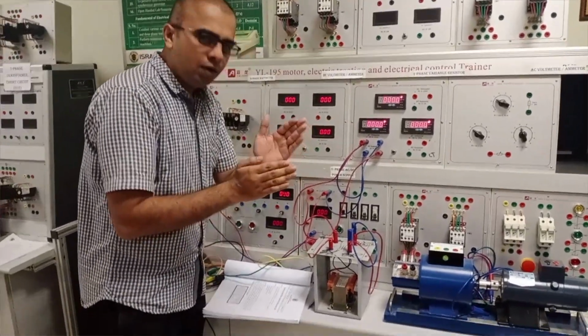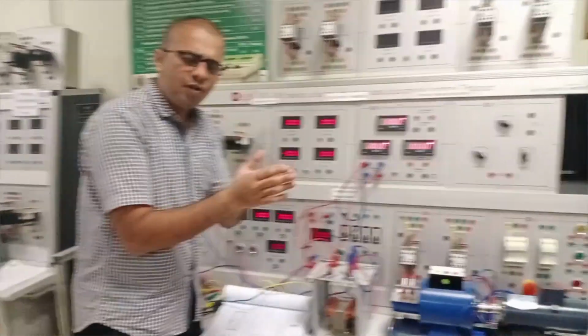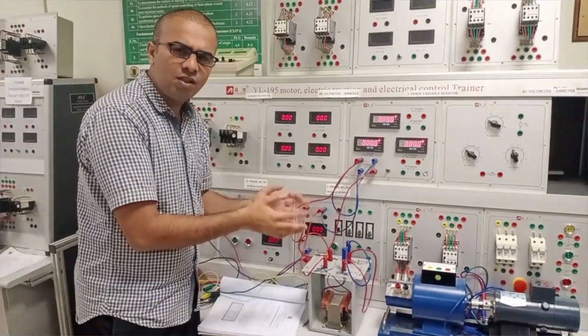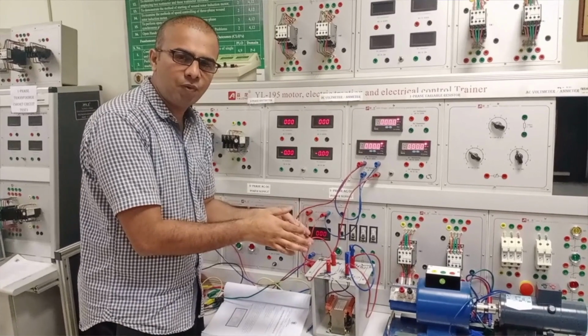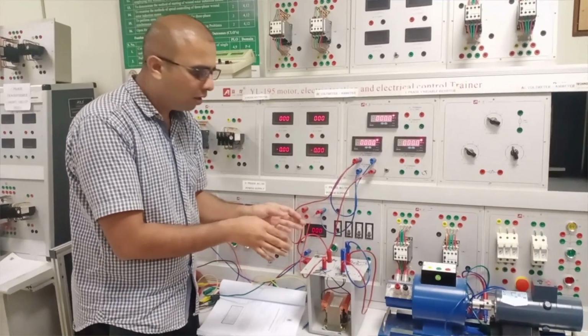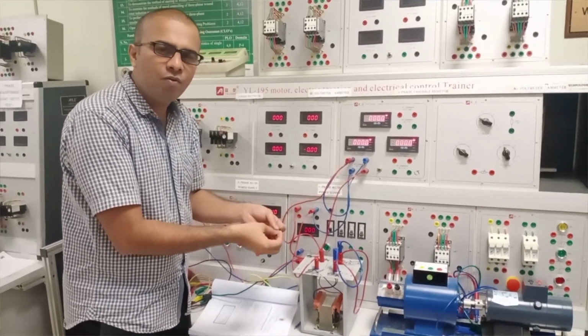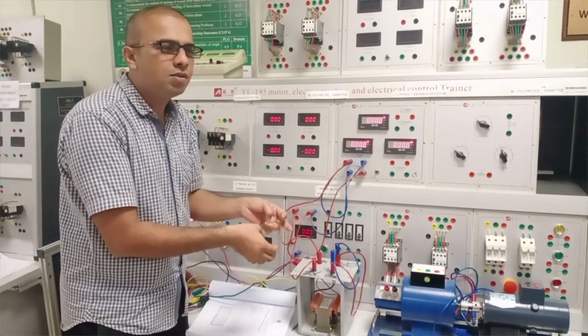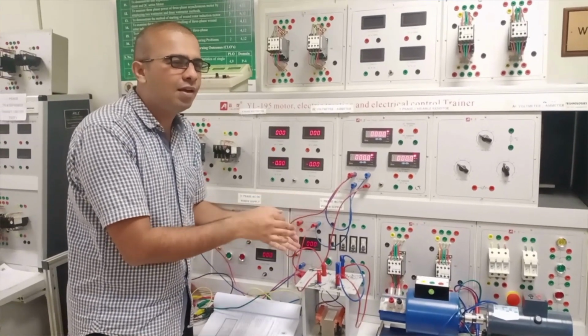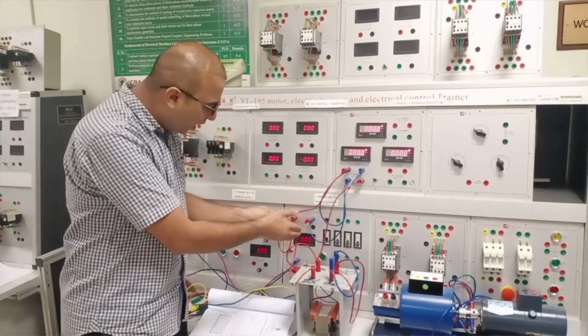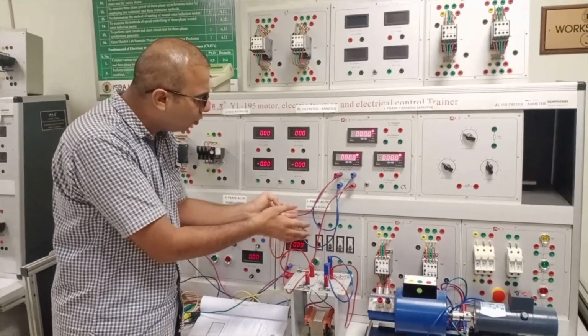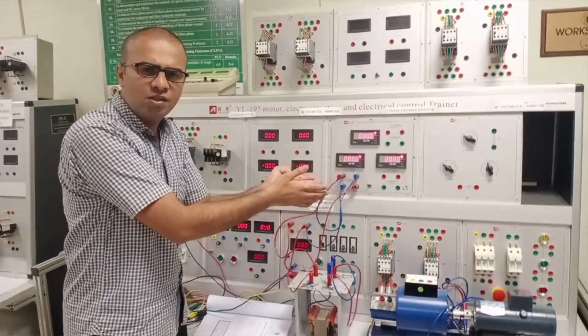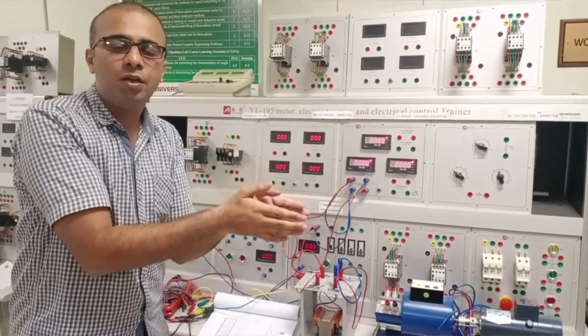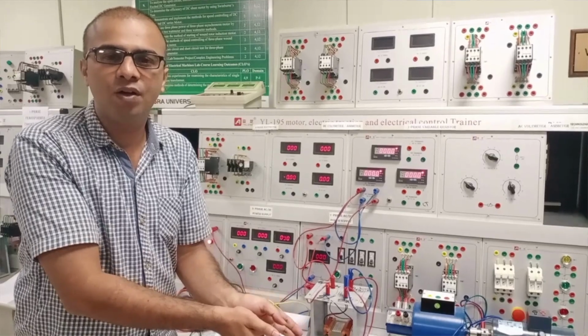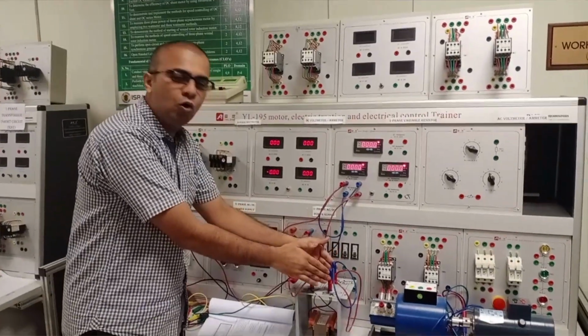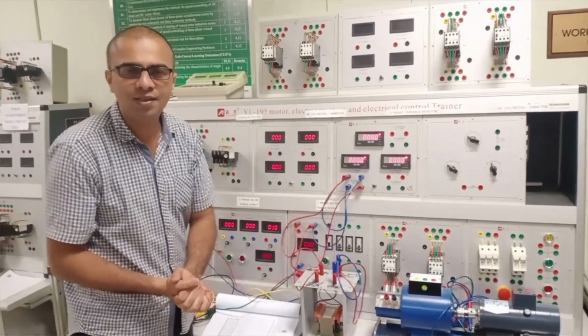Now 5 to 10% of the rated voltage, where 127 volt is the maximum voltage to be given to this transformer on the primary side. If we give a nominal 100 volts to this transformer, then 5 to 10% will be like 5 to 10 volts. Up to that 5 to 10 volts or 12 volts, the full load current starts flowing from the windings of the transformer. That full load current will be called the copper losses in the transformer, because the low voltage winding is kept short circuited in this experiment.